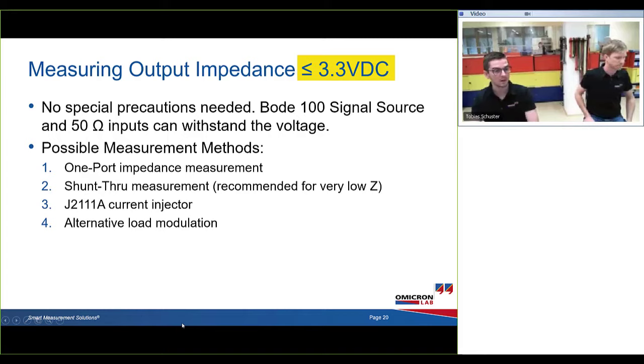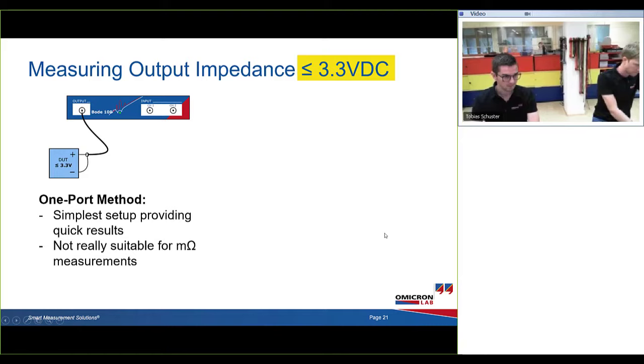Therefore, the possible measurement methods that you have are, first, the easiest one, the one-port impedance measurement. You can use a shunt-through measurement or the extended shunt-through measurement method. This is recommended for very low impedances. Then also a very easy setup is using the PICOTEST current injector J2111A, or you can use every alternative load modulation. Examples: the one-port method, so only the output of the Bode 100 is connected to the output of the VRM. That's the easiest setup, but it's not really suitable if you have very low impedances in the milliohm range. We will also do a live measurement afterwards using the one-port method.